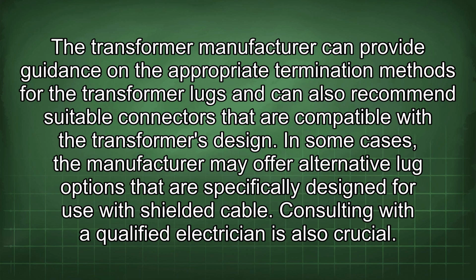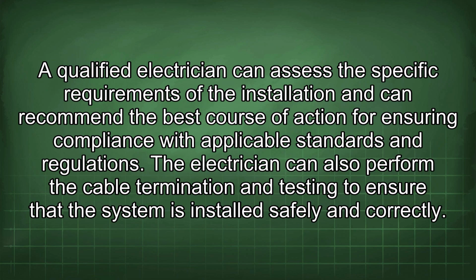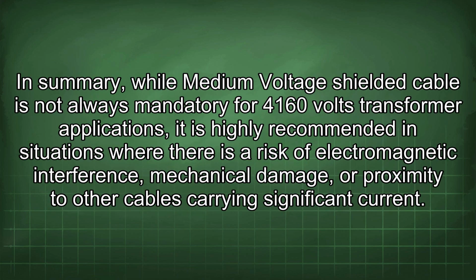Consulting with a qualified electrician is also crucial. A qualified electrician can assess the specific requirements of the installation and can recommend the best course of action for ensuring compliance with applicable standards and regulations. The electrician can also perform the cable termination and testing to ensure that the system is installed safely and correctly. In summary, while medium voltage shielded cable is not always mandatory for 4160 volts transformer applications, it is highly recommended in situations where there is a risk of electromagnetic interference, mechanical damage, or proximity to other cables carrying significant current.